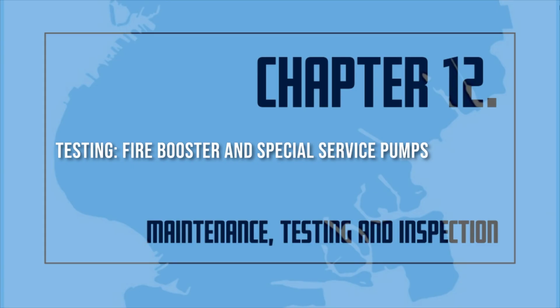B. Fire booster and special service pumps. Pump operation. A weekly test of fire pump assemblies shall be conducted without flowing water and shall be conducted by starting the pump automatically. An electric pump shall run a minimum of 10 minutes and diesel pumps shall run a minimum of 30 minutes. An annual test of each pump assembly shall be conducted under minimum, rated, and peak flows of the fire pump by controlling the quantity of water discharged through approved test devices.